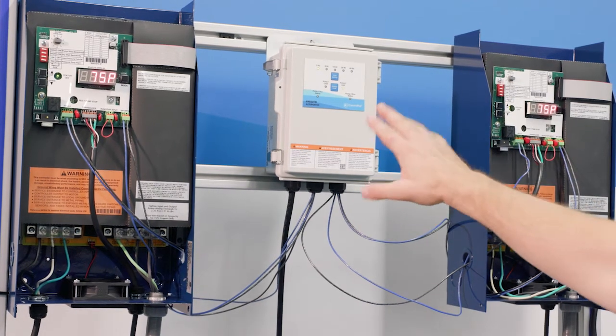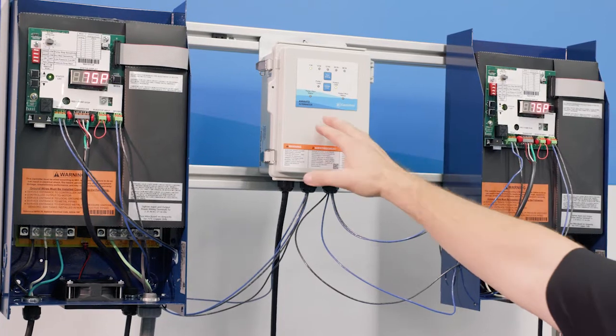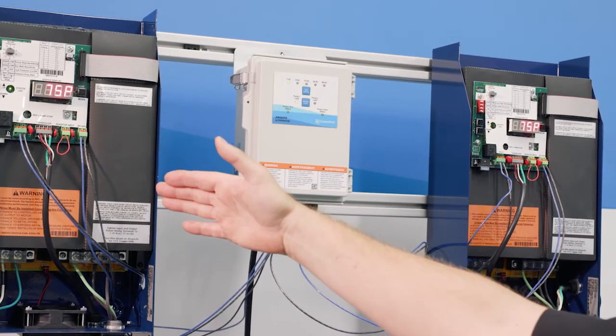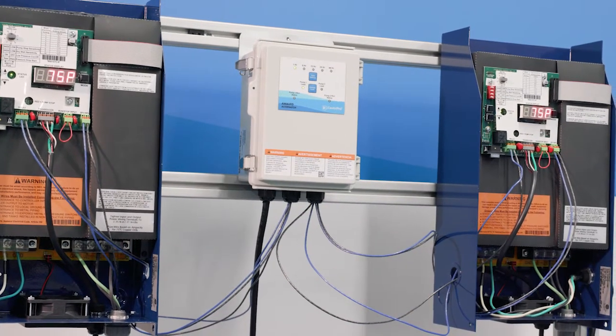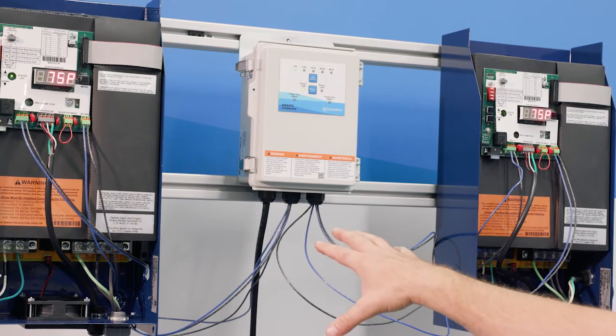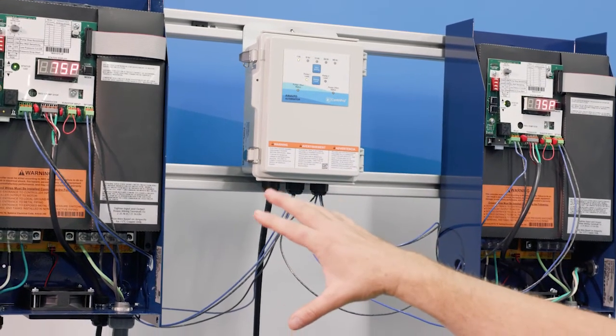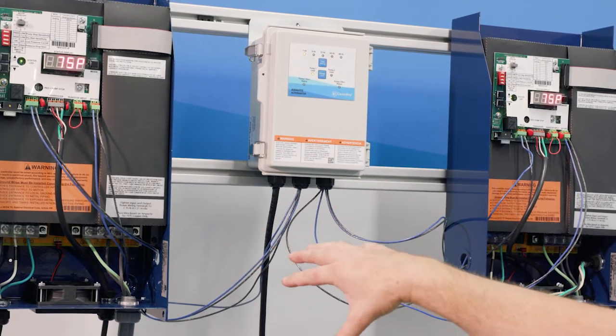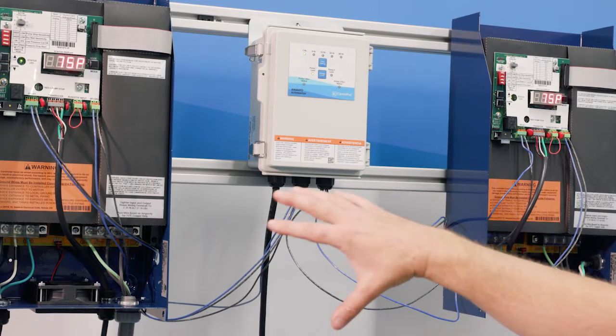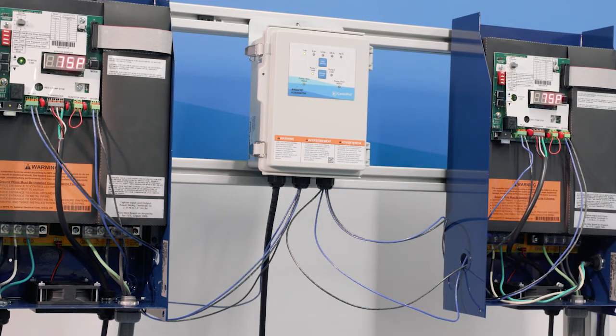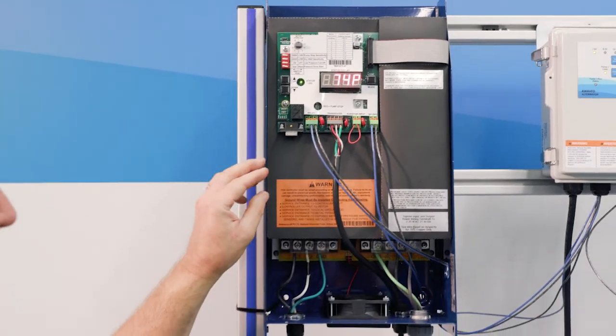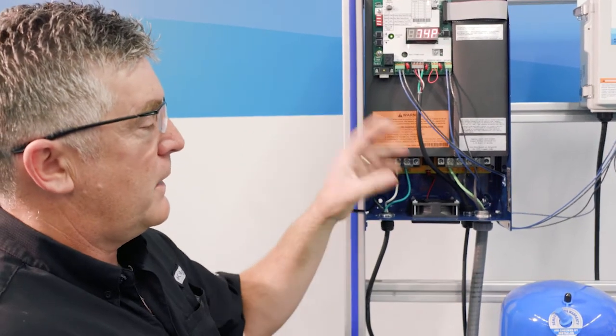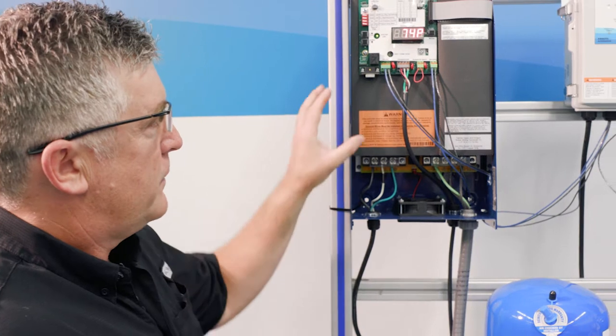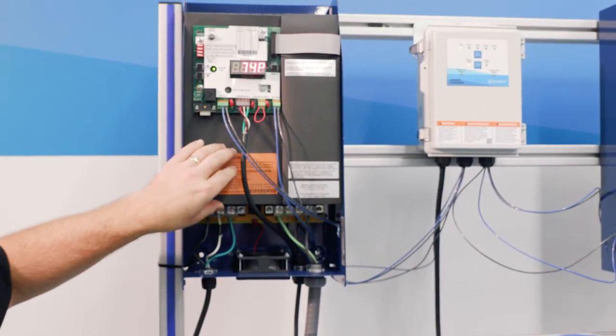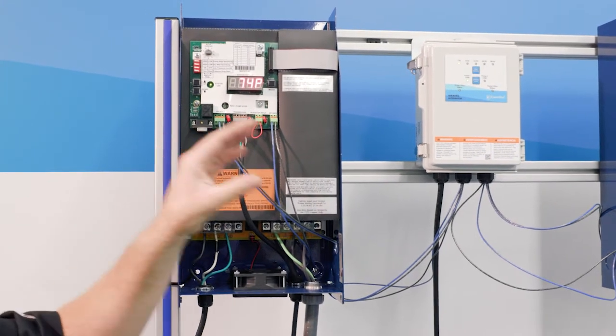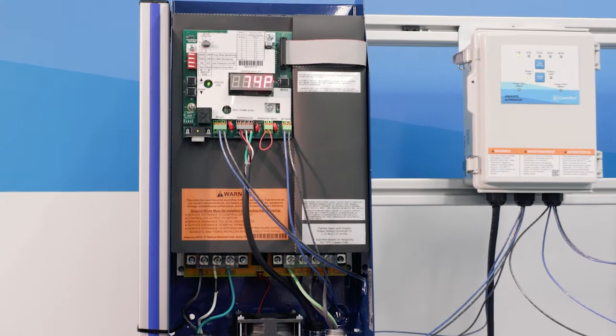So a couple things that we can do. We could change that lead lag anytime you want, simply by pressing the button, and so now we've got our lead over here. The other thing that's unique about this is, let's say that our lead pump, lead system, lead drive is off. What happens is it automatically changes from lag to lead. So let's try that. This is the unit on the left, and it's currently set to lead, which means the unit on the right defaults to the lag. So let's see what happens when something goes wrong with the lead, and we'll see if it turns the lag into the lead.